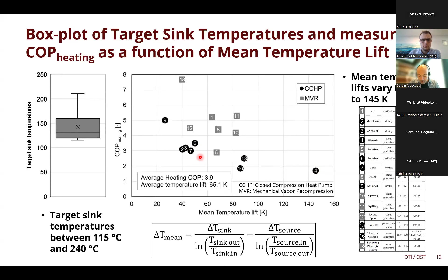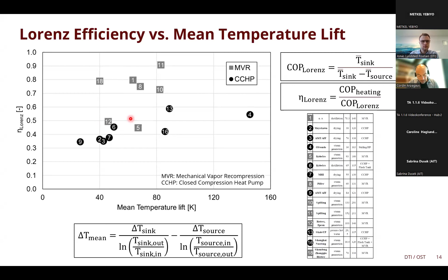Here, this graph shows the Lorenz efficiency, which is the theoretical maximum efficiency, versus the temperature lift again. Here first for the closed cycle heat pumps, we have ranges of, let's say, 40 to 50%. And then when we include the MVR systems, we have achieved Lorenz efficiencies of up to 70 to 80%.